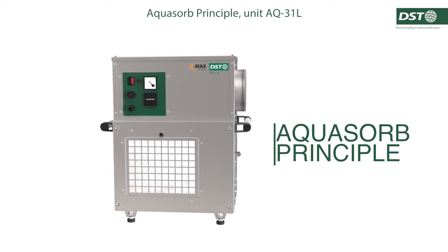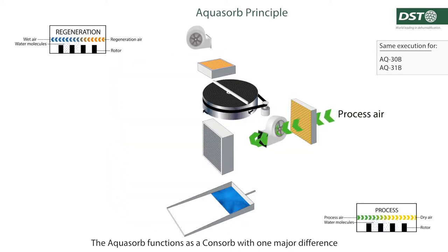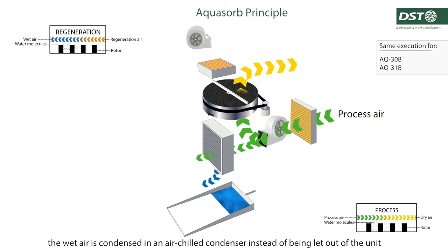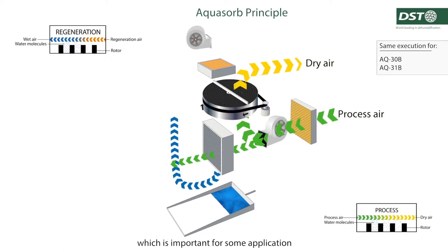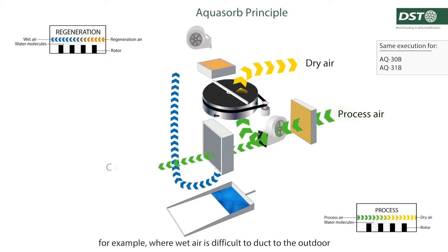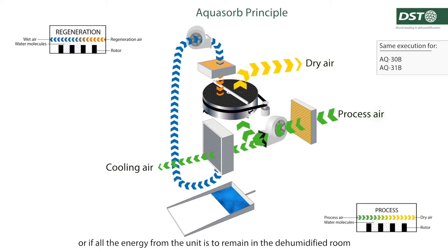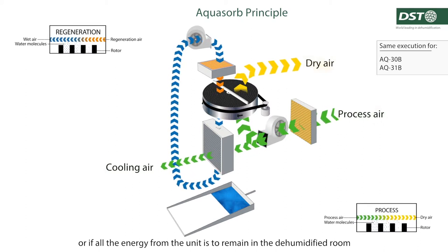Aquasorb principle. The Aquasorb functions as a Consorb with one major difference. The wet air is condensed in an air-chilled condenser instead of being let out of a unit, which is important for some applications. For example, where wet air is difficult to duct to the outdoor, or if all the energy from the unit is to remain in the dehumidified room.